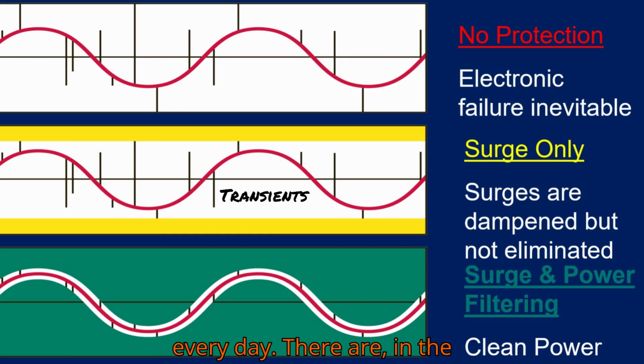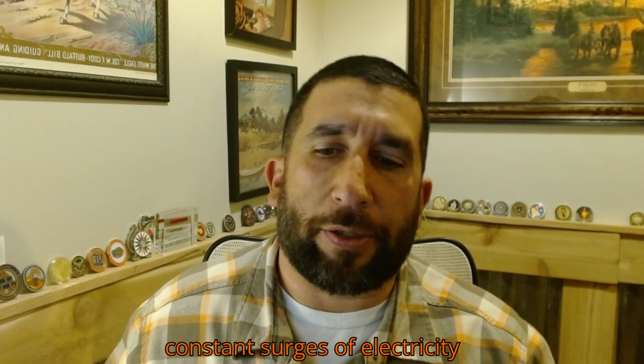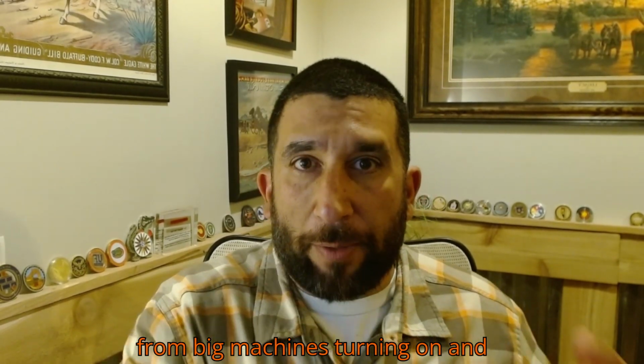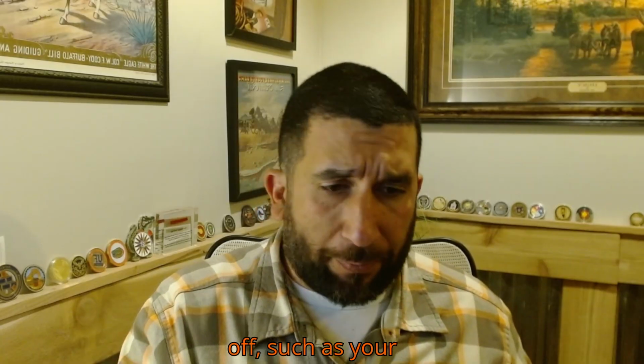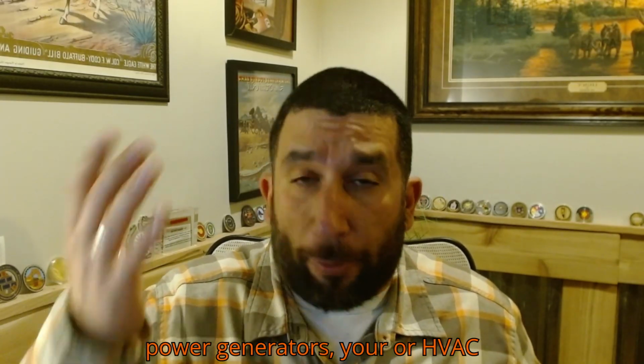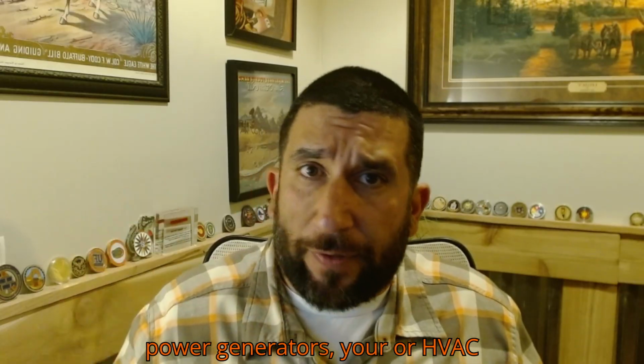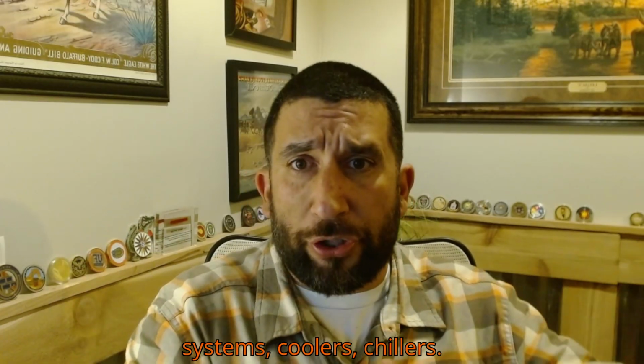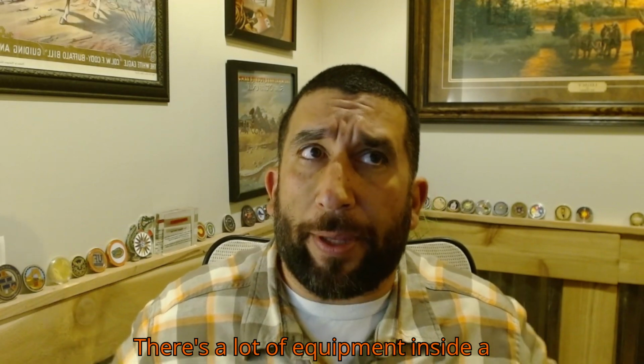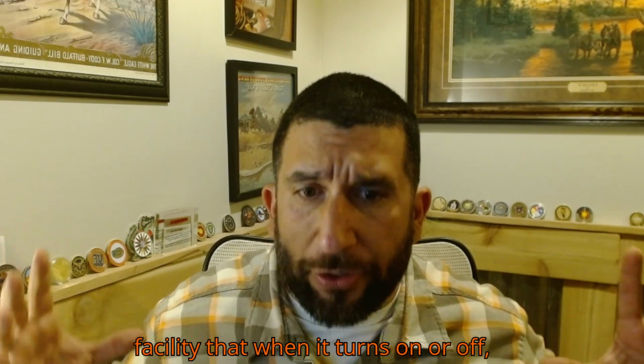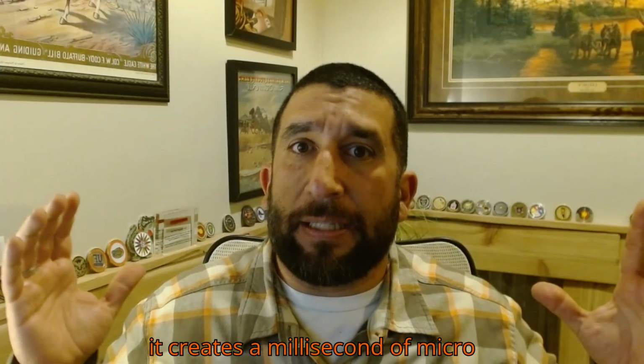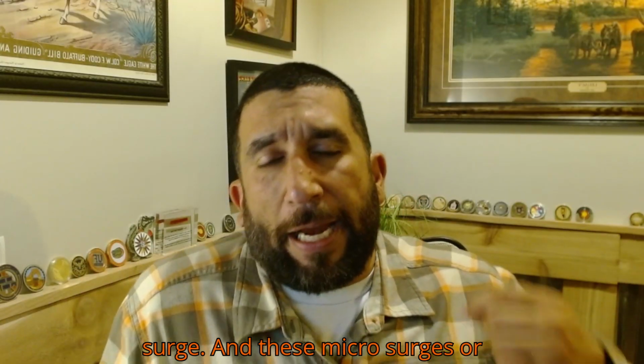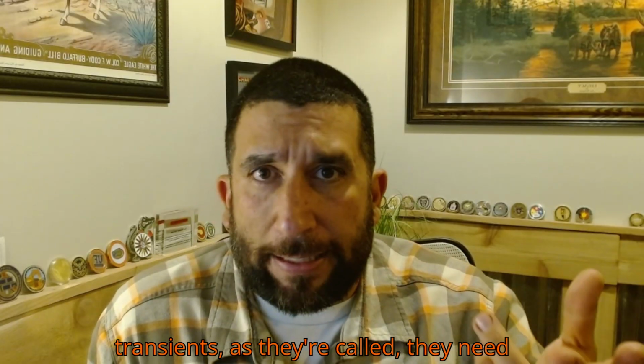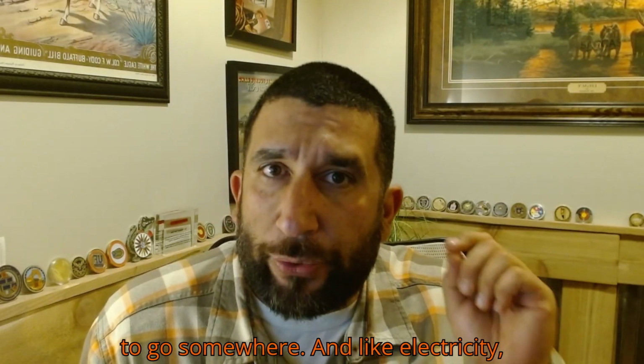In the electrical field, within the alternating current of a facility, you have constant surges of electricity from big machines turning on and off, such as power generators, HVAC systems, coolers, chillers. A lot of equipment inside a facility creates a millisecond microsurge when it turns on or off, and these microsurges, or transients, need to go somewhere.